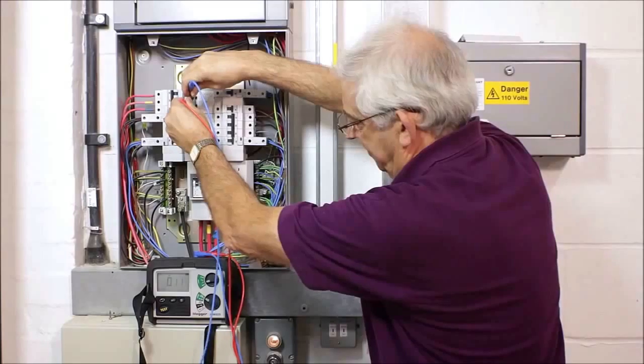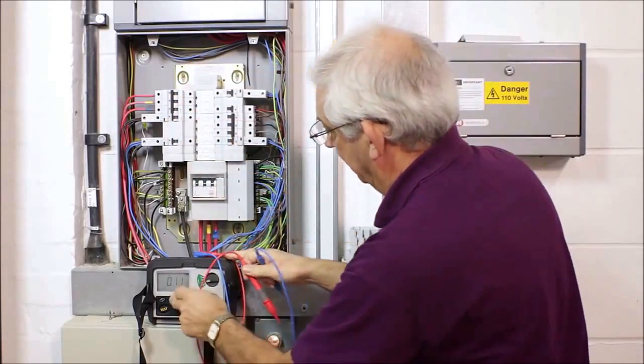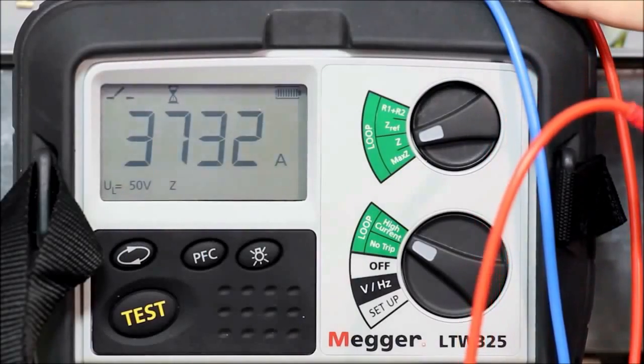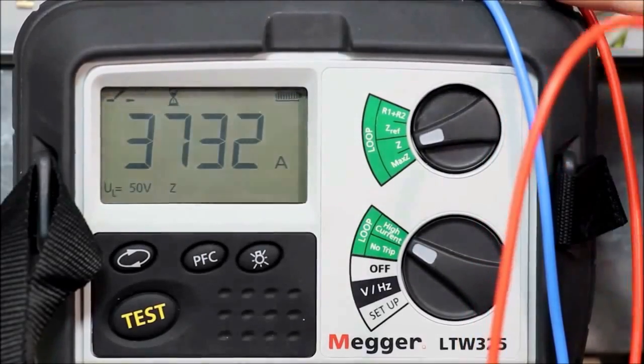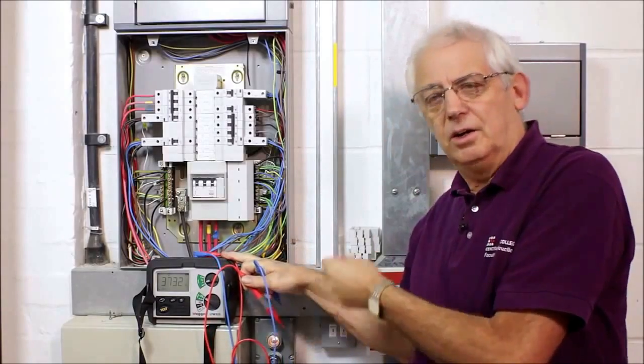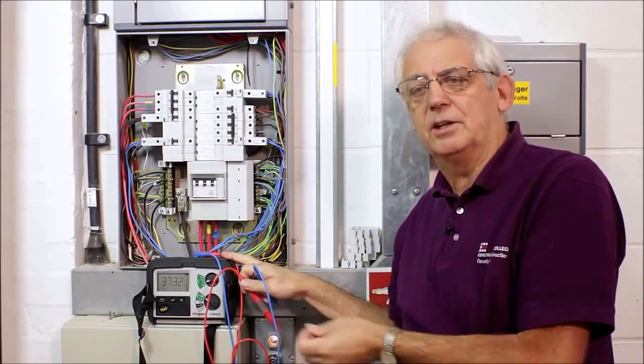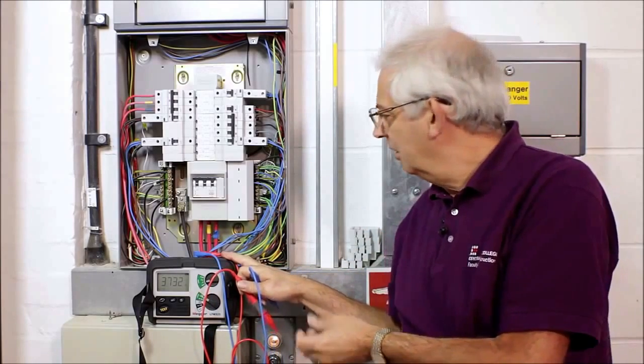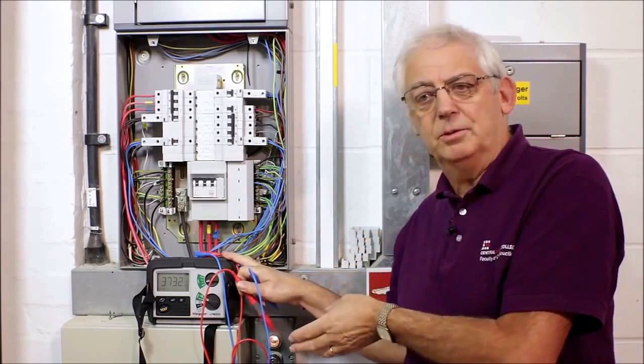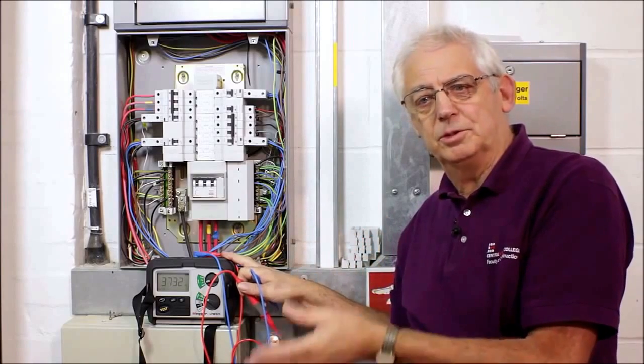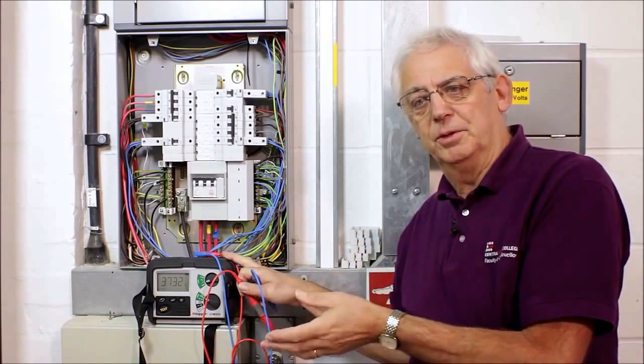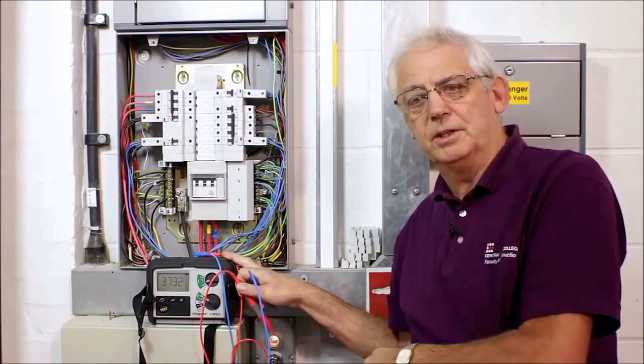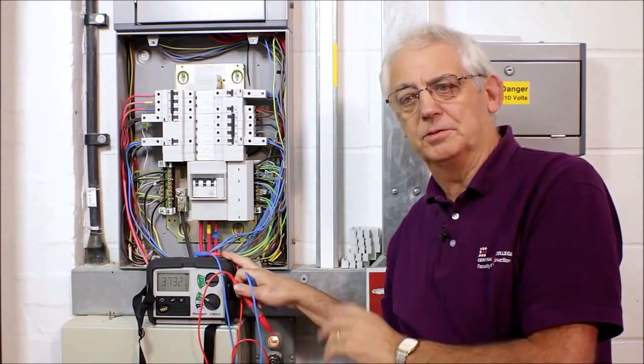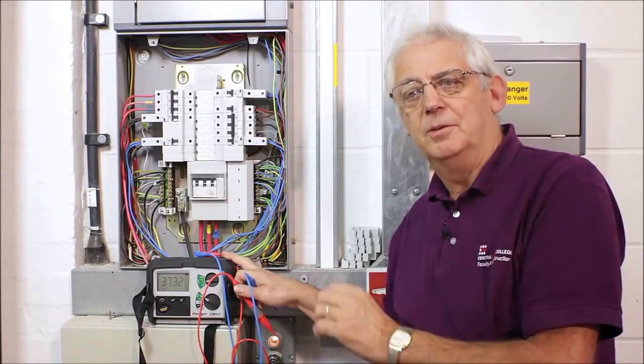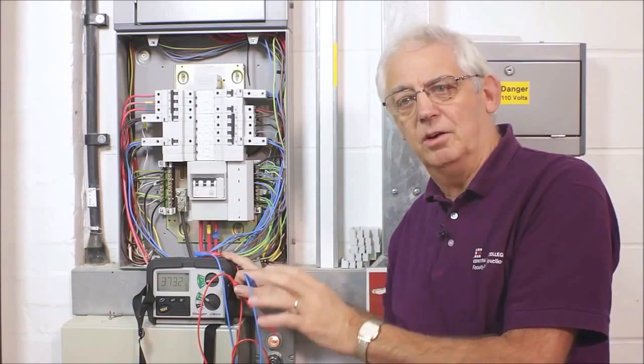4,148, yellow and blue, 3,732. So the highest value there I could put down as quite an accurate reading for PFC, although as you saw the value of line to neutral doubled was slightly higher, which is always going to be on the right side. So whichever way you do it is perfectly acceptable as far as the regulations are concerned, because the value between line and neutral is always going to err on the side of safety.